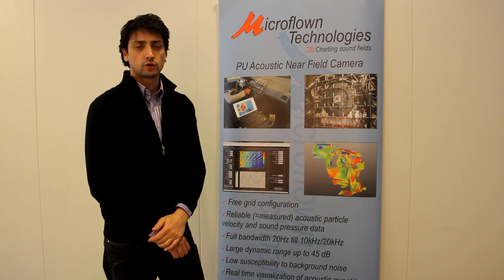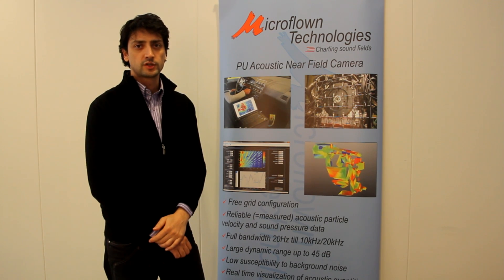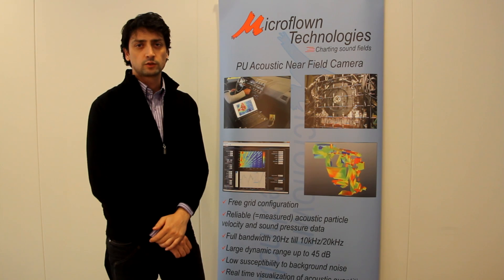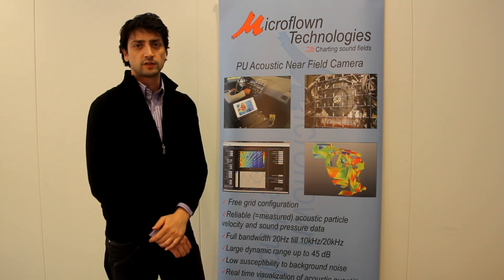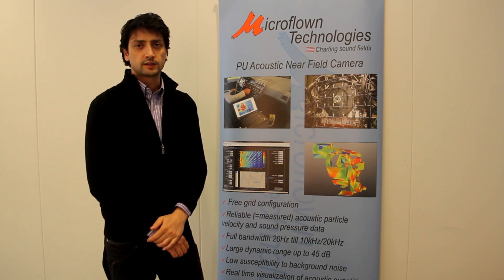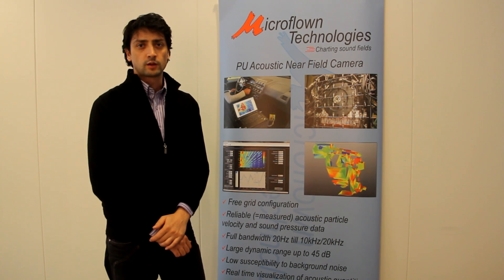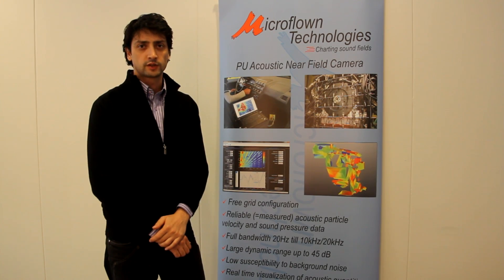Transient noise is a noise that changes over time, like for example a startup of a machinery, a door slam, or a run-up of an engine. To be able to map the sound in this condition it is necessary to use a multiple probe solution and a multiple channel frontend. The alternative is to relate the measurement to some working condition of the machinery, but this requires an additional reference channel and complex methods for the calculation.